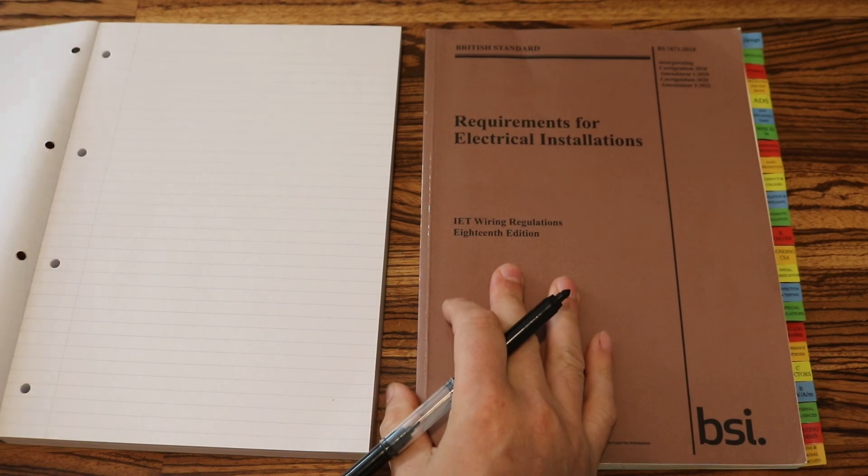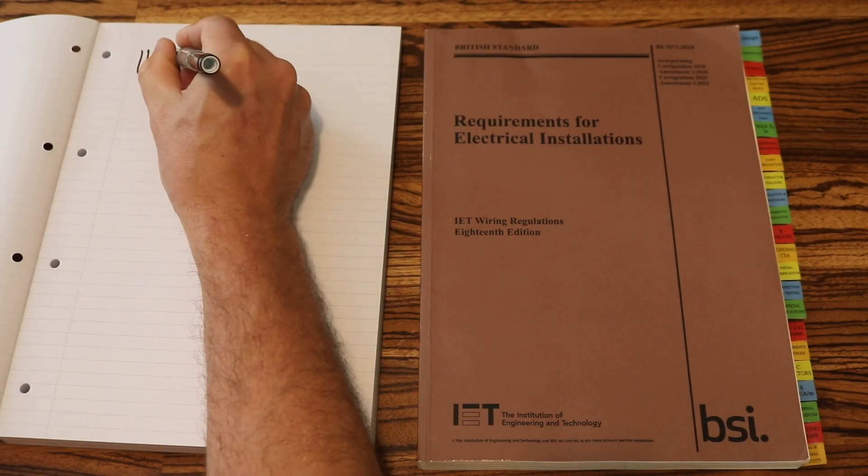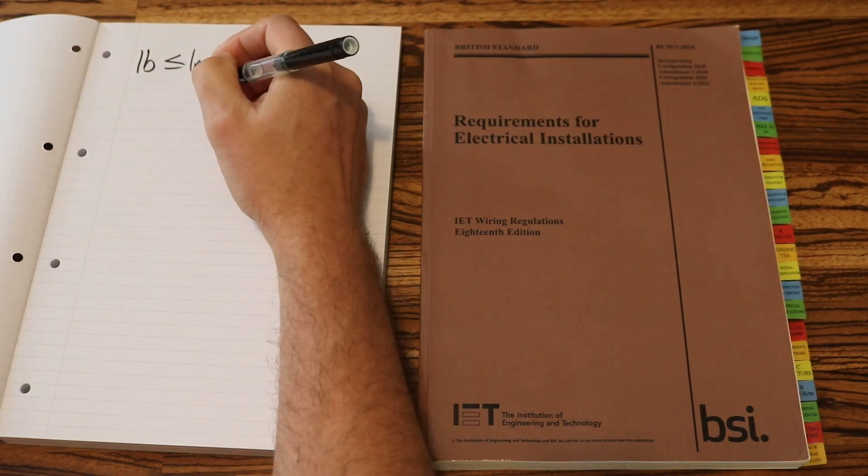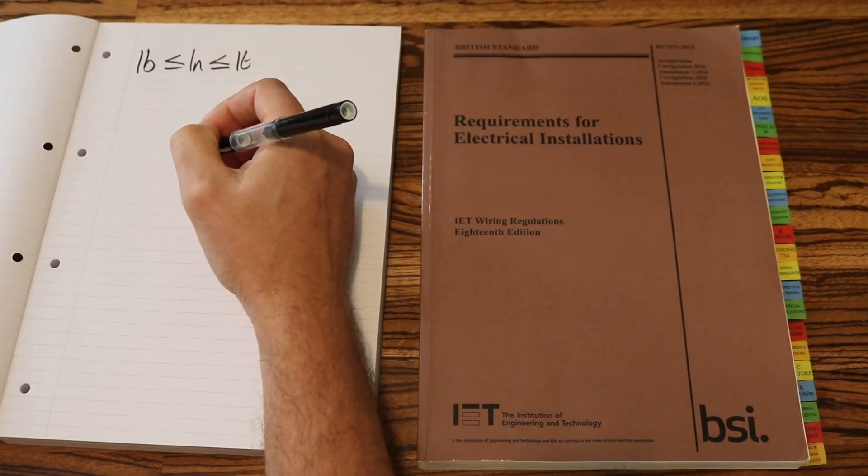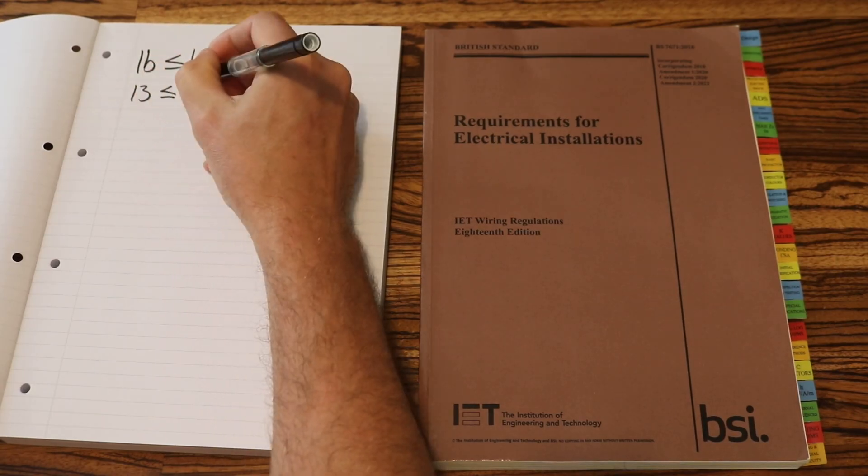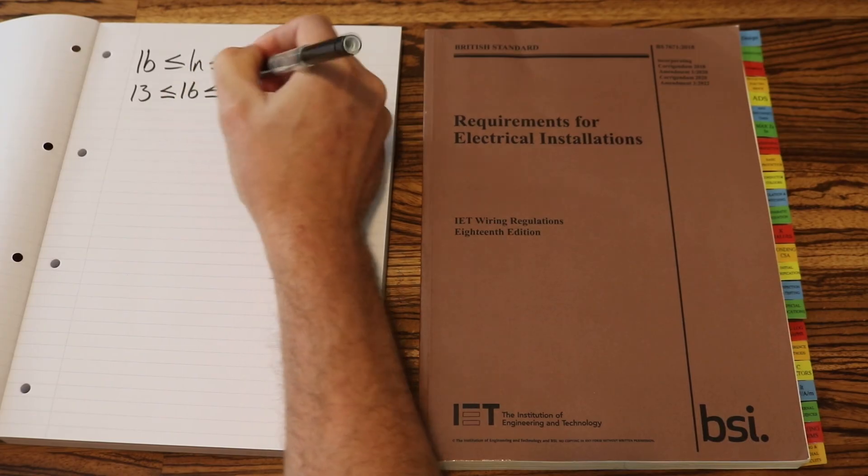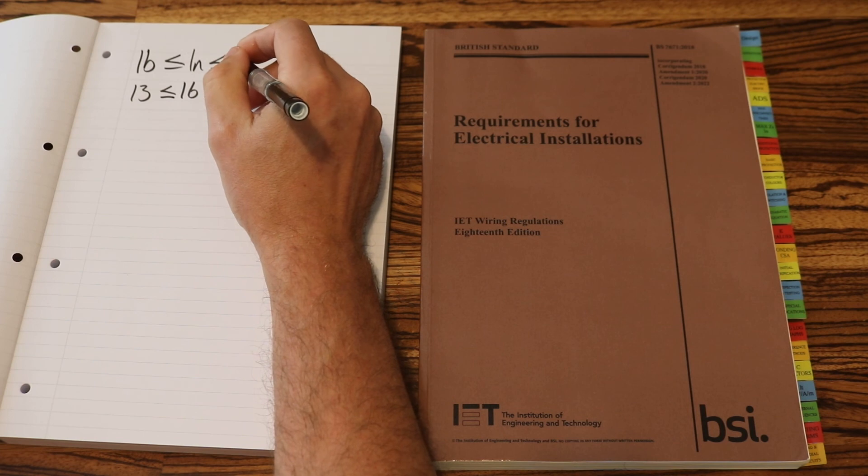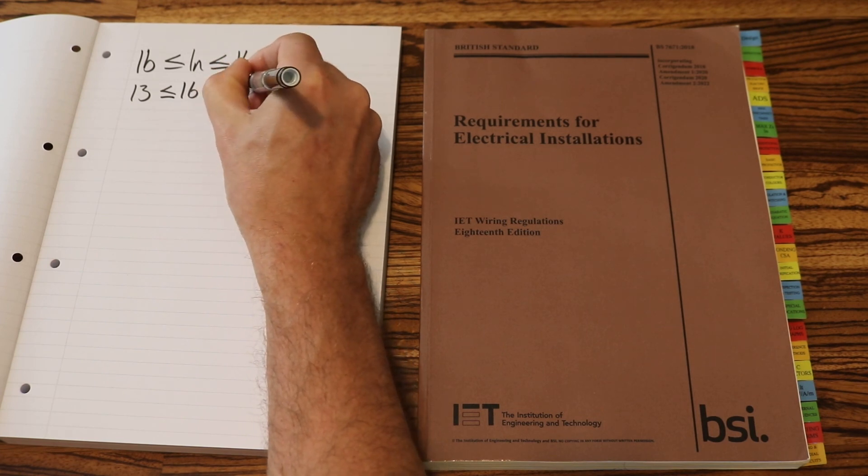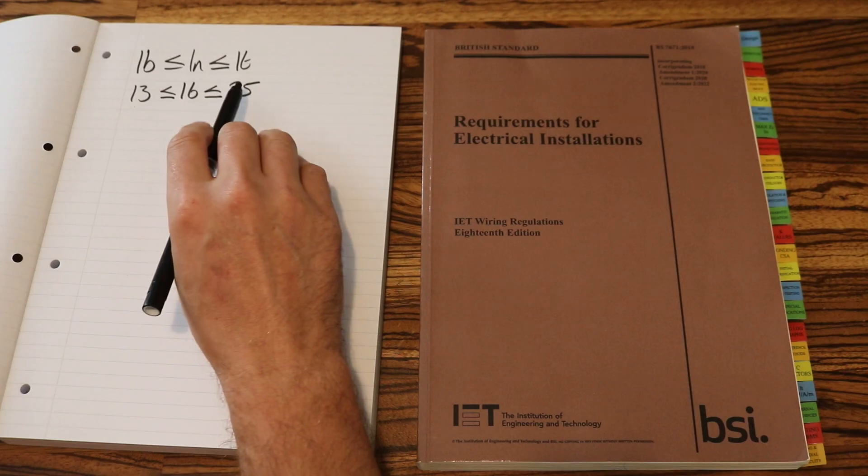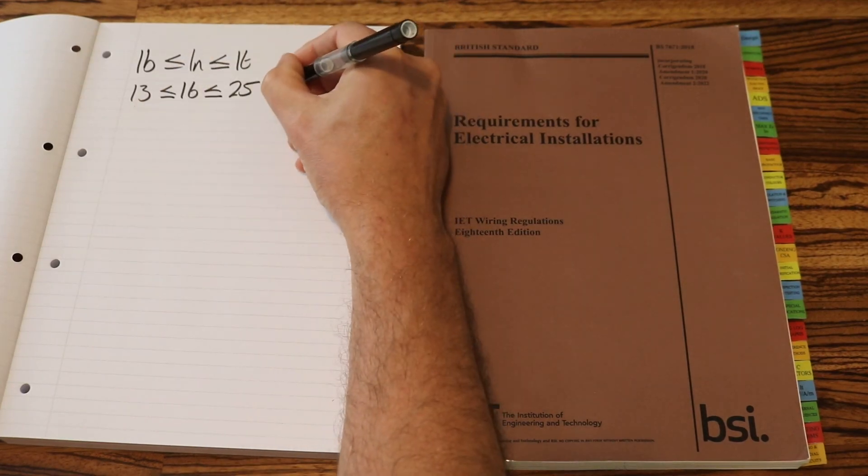Our last bit of cable calculation. Remember, it's not really a formula, it's more like a statement. IB is equal to less than IN, which is equal to less than IT. Let's input our values. So that was 13, IN was 16, and our IT was 25. So is 13 equal to less than 16? Which it is, and 16 equal to less than 25. Which it is, and that is correct.